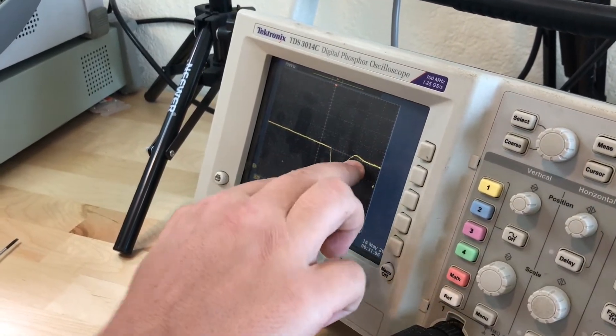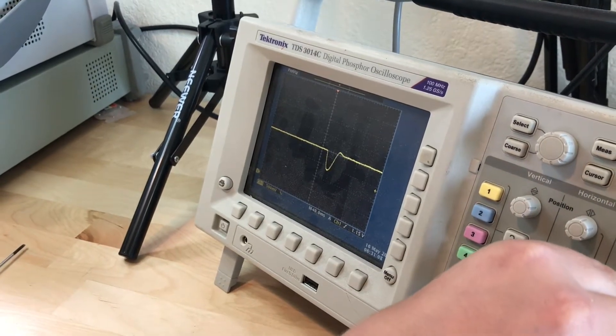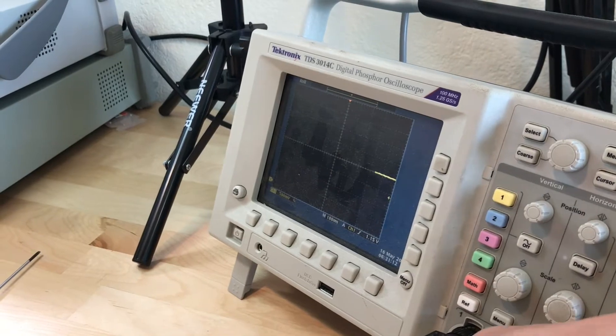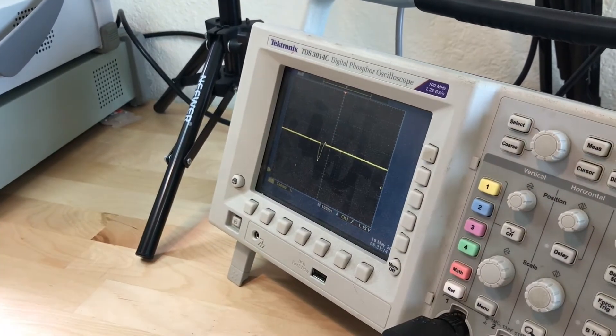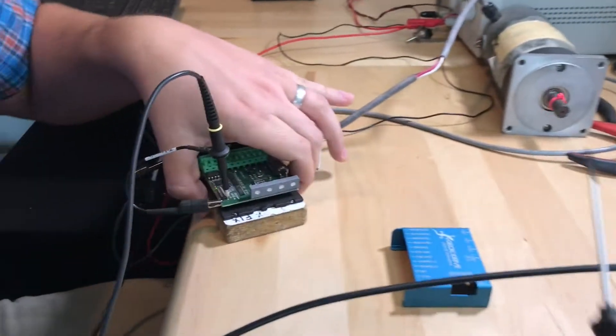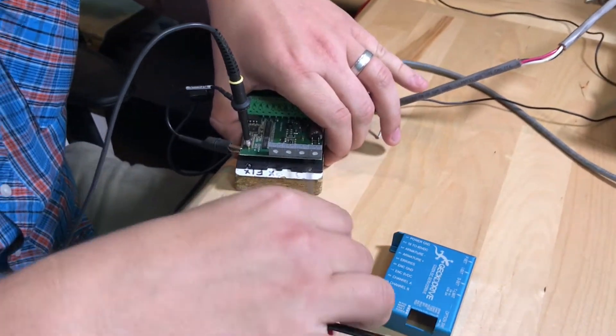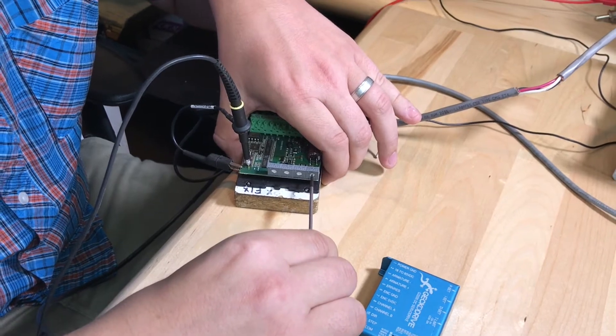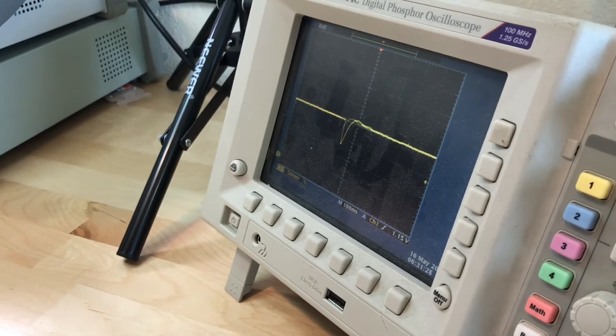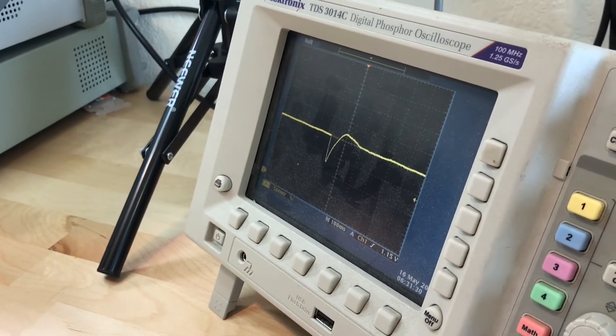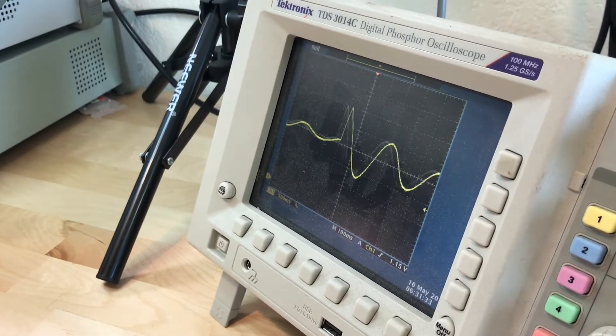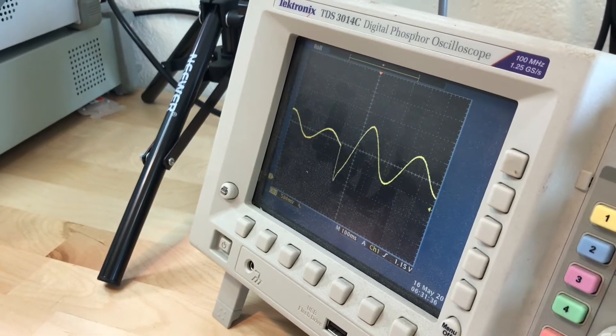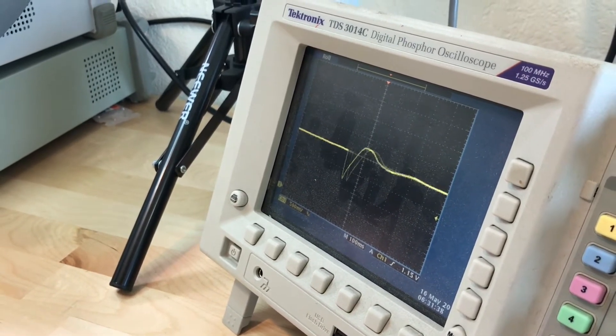Going back to command position. Let me go back to run, stop, and there we go. Going over quickly what each trim pot does: this is the P trim pot. If you look at the oscilloscope as I turn it down, you can see it increases the settling time. That's the proportional of the PID. As I turn it down counterclockwise, it really increases the settling time to infinity if you turn it all the way.